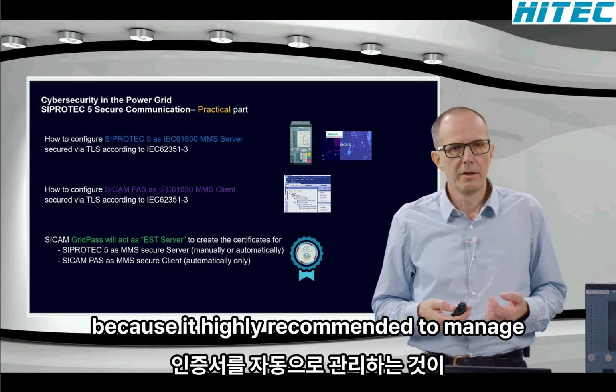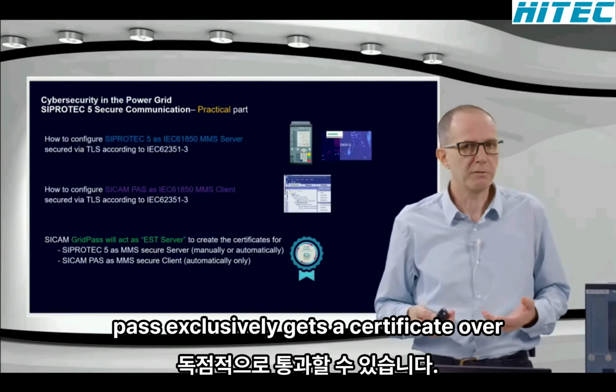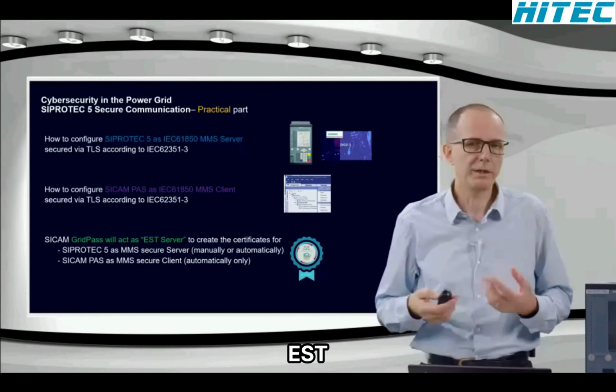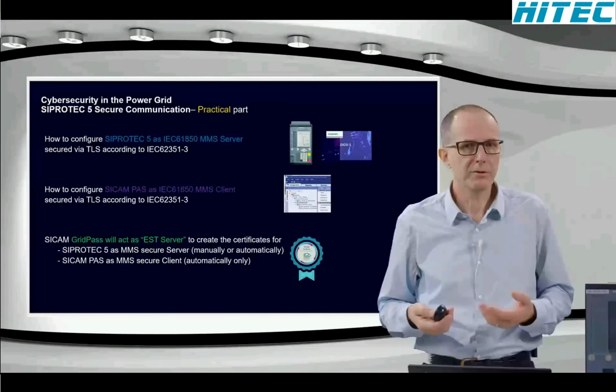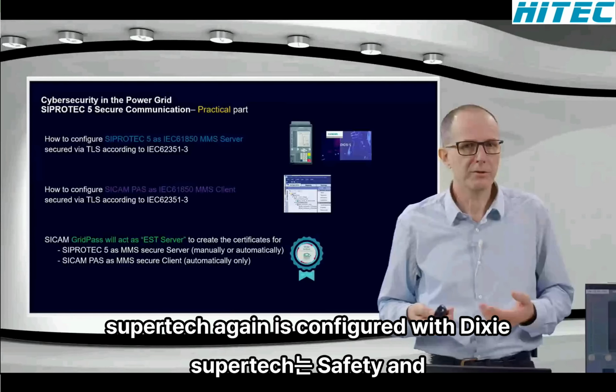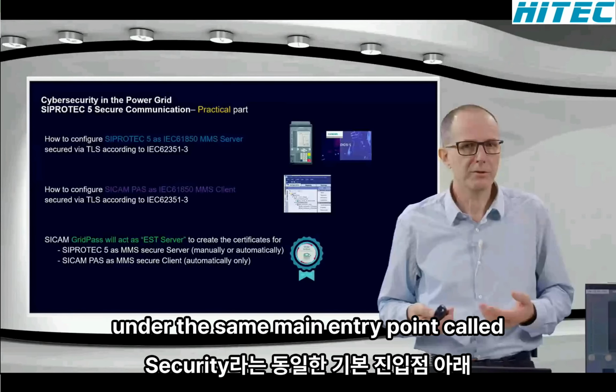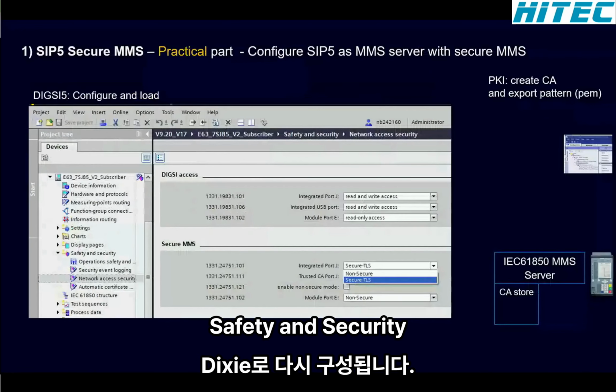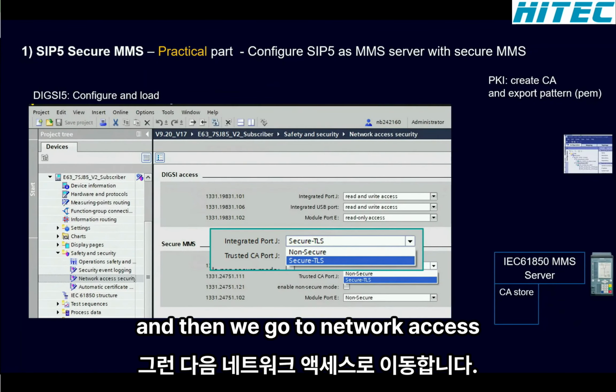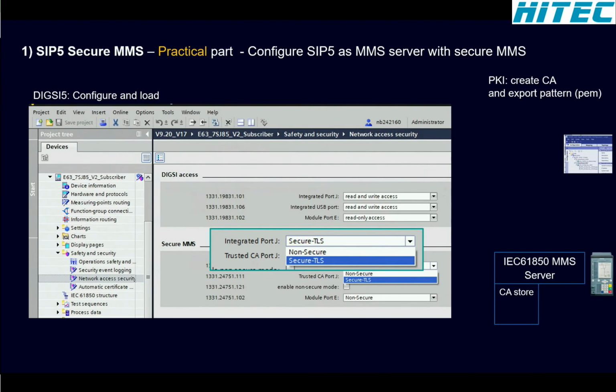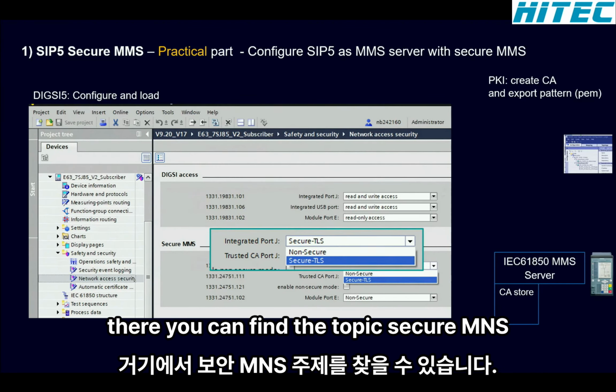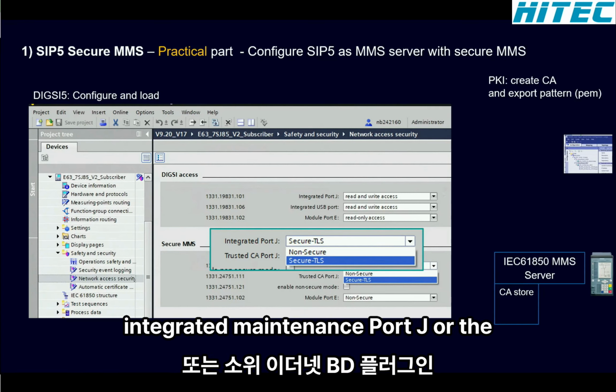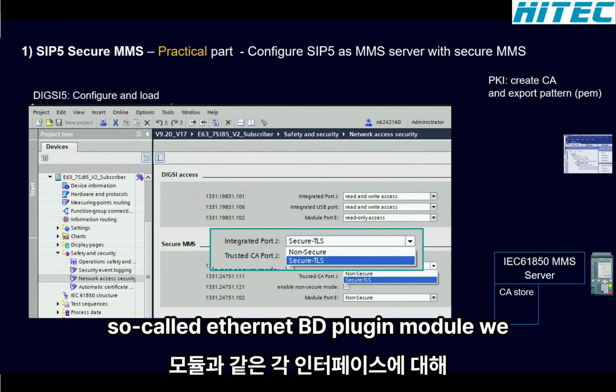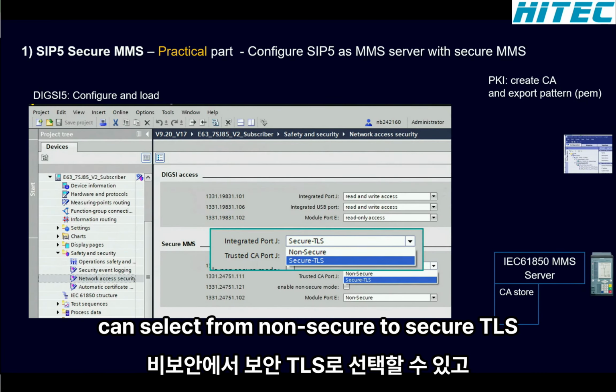Because it's highly recommended to manage the certificates automatically, SICAM PAS exclusively gets the certificate over EST. SIPROTEC, again, is configured with DIGSI under the same main entry point called Safety and Security. Then we go to Network Access Security. There you can find the topic Secure MMS. For each interface, for example the integrated maintenance port J or the so-called Ethernet plug-in module, we can select from non-secure to secure TLS.